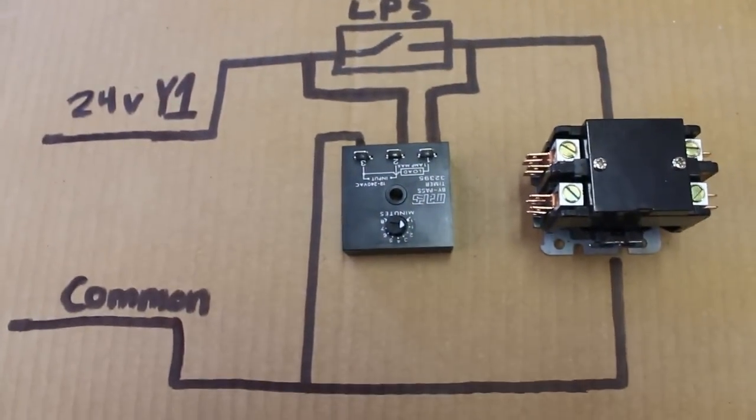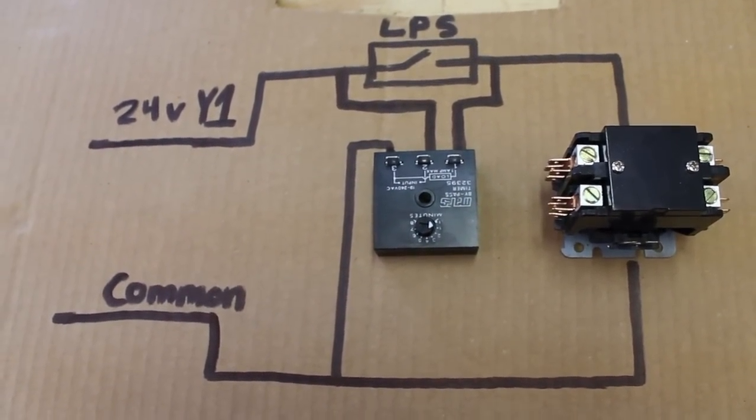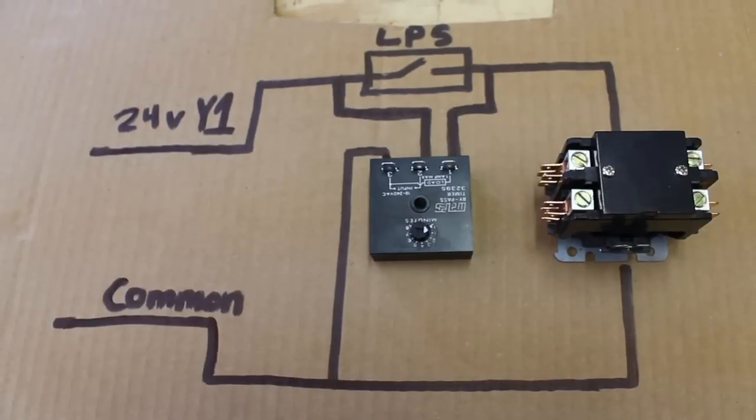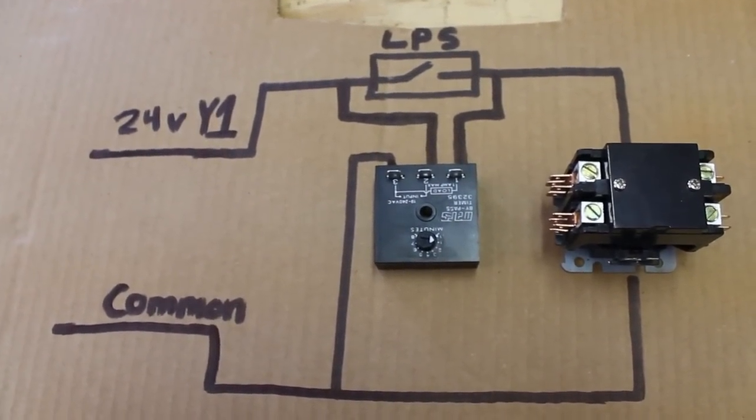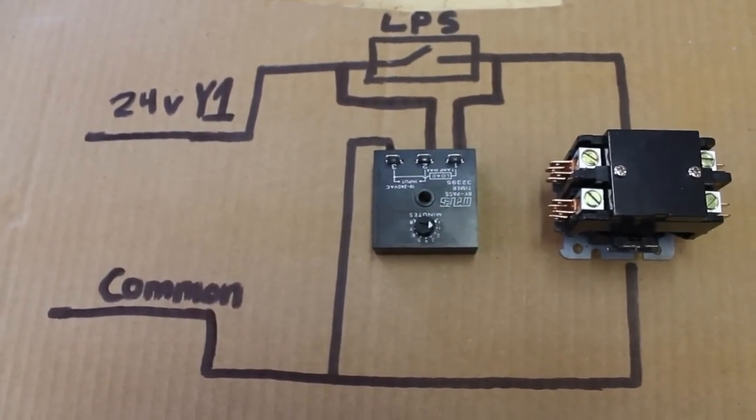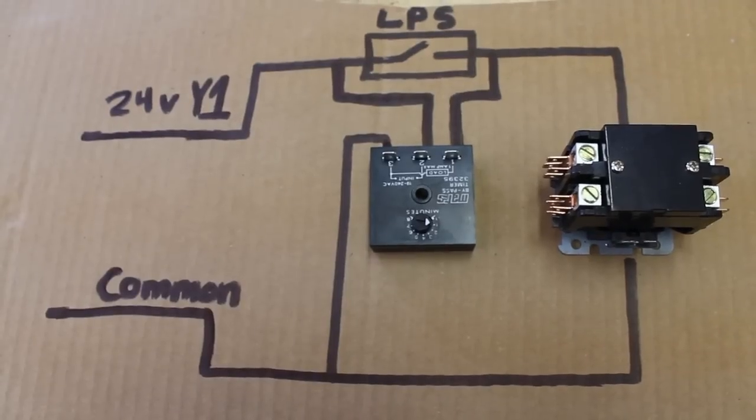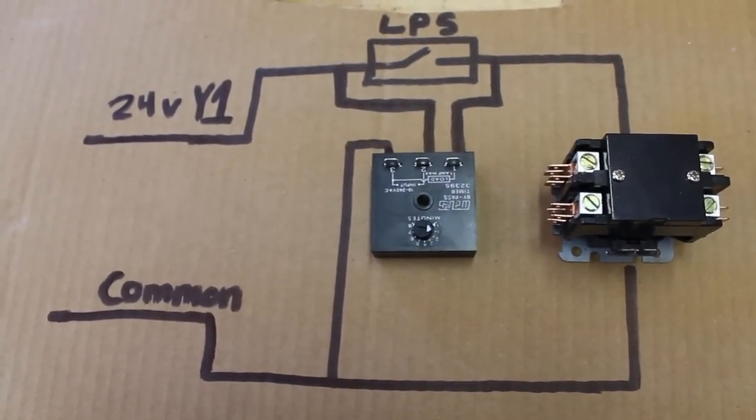So we have a time period where voltage can flow from Y1 all the way to the contactor uninterrupted by the low pressure switch. After that time period of six seconds to eight minutes, it will then be at the liberty of the switch. That is how the bypass timer is wired in and one application you can use it for in air conditioning.